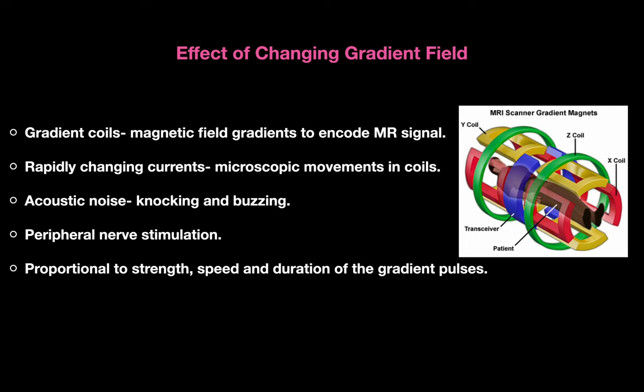The changing gradient field: gradient coils produce magnetic field gradients to encode MR signals using x, y, and z coils. Rapidly changing current inside these coils produces microscopic movement causing knocking and buzzing, which can cause peripheral nerve stimulation. This depends proportionally on the strength, speed, and duration of the gradient pulses. Activation of the gradient coils can cause noise leading to temporary hearing impairment, and in a few studies there is potential for permanent hearing impairment.